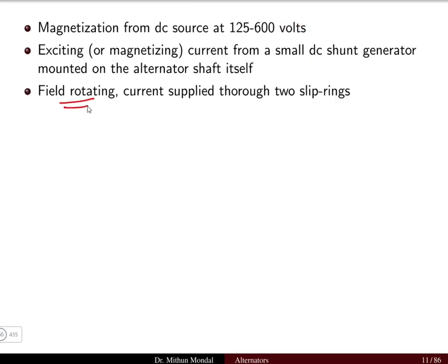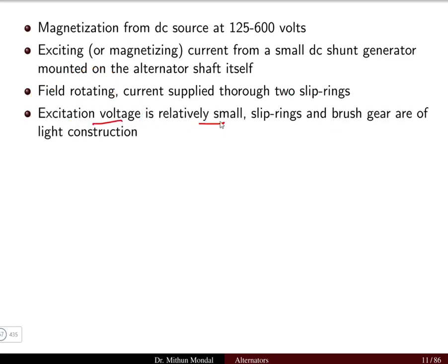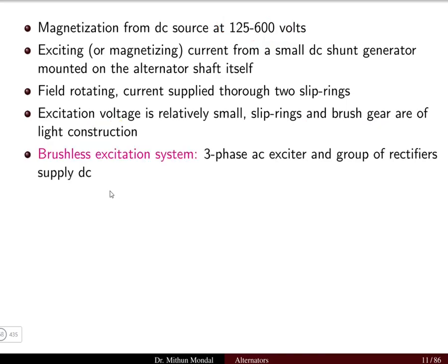Since the field is rotating, the current is supplied through two slip rings. The excitation voltage is relatively small at 125 to 600 volts, so the slip ring and brush gear are of light construction, making the overall construction simpler compared to a DC machine. In another excitation system, known as brushless excitation, a three-phase AC exciter and a group of rectifiers are used to supply the DC.